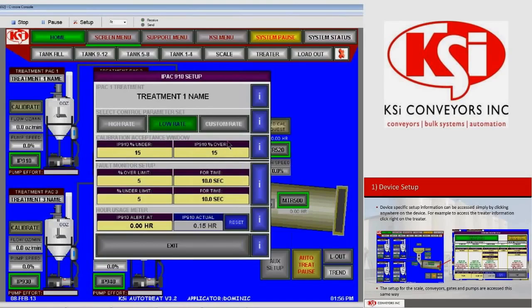The next 2 parameters are the calibration acceptance window. In this case, it's an IP 910% under and an IP 910% over, and these are both at 15%. And what this window does is it only comes into play when we're calibrating the pump. If we're calibrating our pump and we end up with 75 ounces in our cow tube and our flow meter reads 60 ounces, we're over 15% off in that error. And if we try to enter that, it's not going to let us, and it's going to error out.